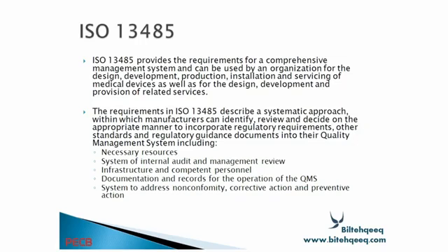The requirements of ISO 13485 describe a systematic approach within which a manufacturer can identify, review and decide on the appropriate manner to incorporate regulatory requirements, other standards, and regulatory guidance documents into the quality management system, including necessary resources, a system of internal audit and management review, infrastructure and competent personnel, documentation and records for operation of the quality management system, and addressing non-conformity, corrective action and preventive actions.